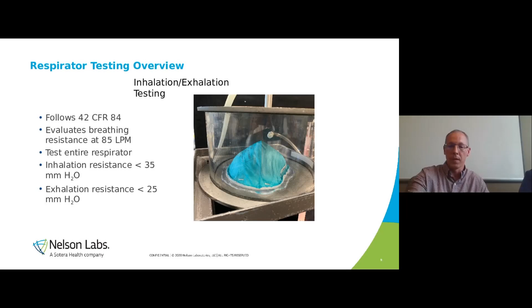If the respirator does have an exhalation valve, we test that valve by cutting it out, removing it from the respirator, mounting it in this test mount here, sealing it up with beeswax to reduce any leakage, and then we try to push air through the exhalation valve. Again, as you breathe in or inhale air, that exhalation valve should seal and not allow air to come through it. So that's what we're testing. If any of these valves allow 30 milliliters per minute of air, it will fail the test. So it must seal and keep air from coming in through that exhalation valve.